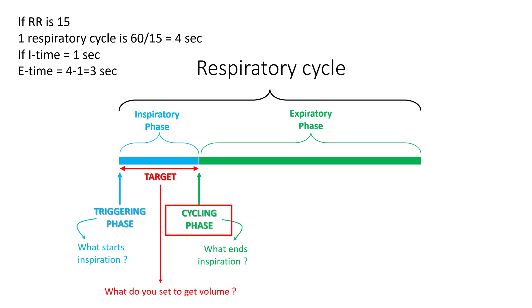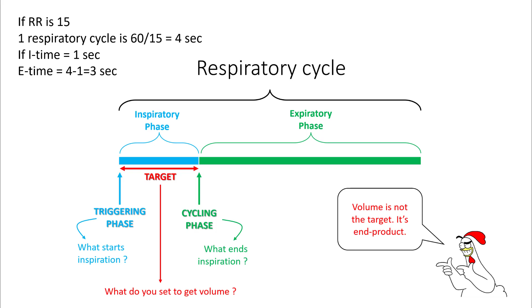As we discussed before, the triggering phase is what starts the inspiration. The cycling phase is what ends the inspiration, and target is what you set to get the volume. And we learned that volume is not the target, but it's the end product. When you are breathing normally, you're generating some tidal volumes, and there are two ways to do it. Either you generate a negative intrapleural pressure or a positive flow, which pushes the air.